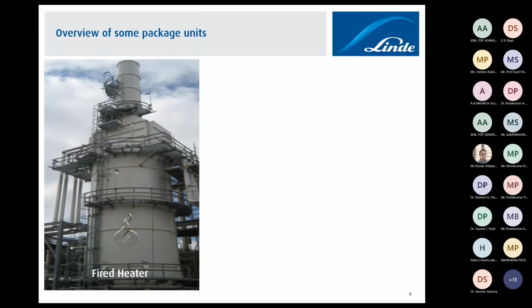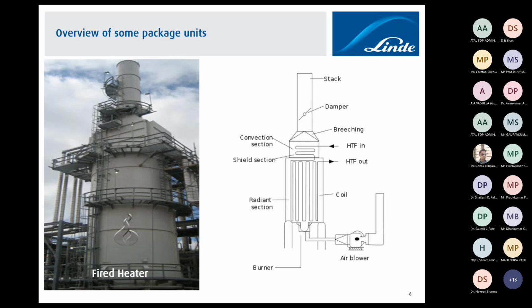Fine, let's move to another piece of equipment, that's a fired heater. This is an industrial view, especially Linde has built this unit in Opal, Dahej. This is a fired heater. So what is the significance of it? Wherever you have a hydrocarbon fluid and you need some heating, some 100-degree or 150-degree heating is needed, of course a heat exchanger may not be able to give that much delta T. So in that case, the equipment called a fired heater, most of the time, is a vertical installation. Of course, in special cases, you can see horizontal installation also.